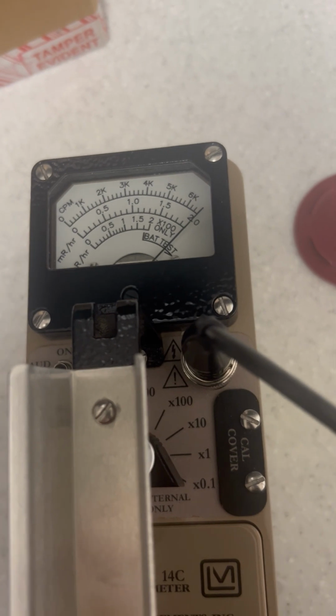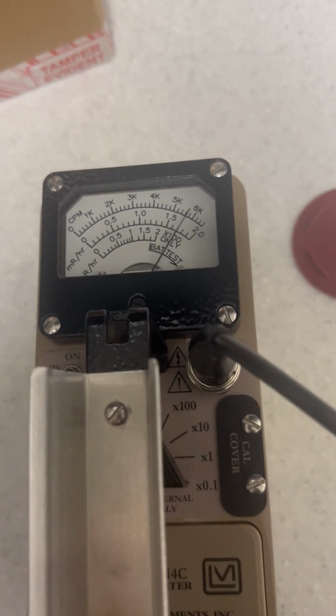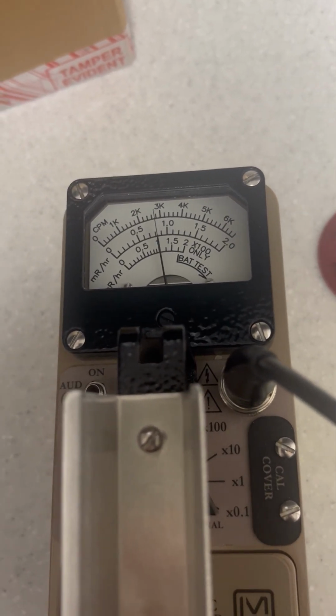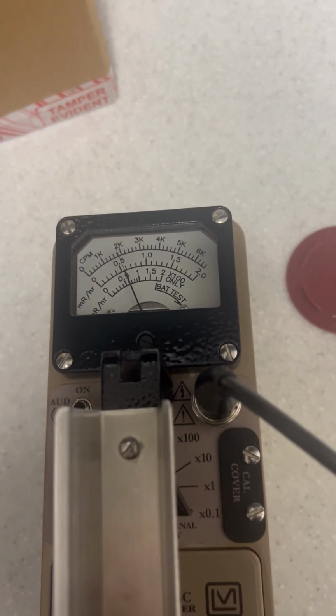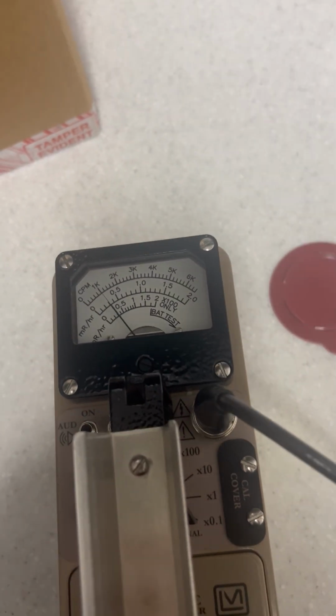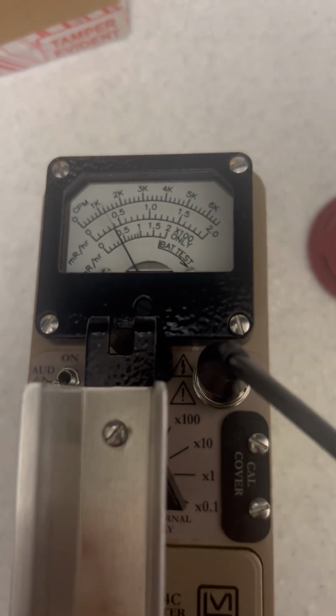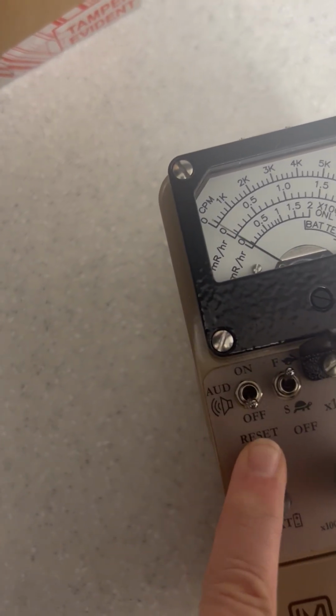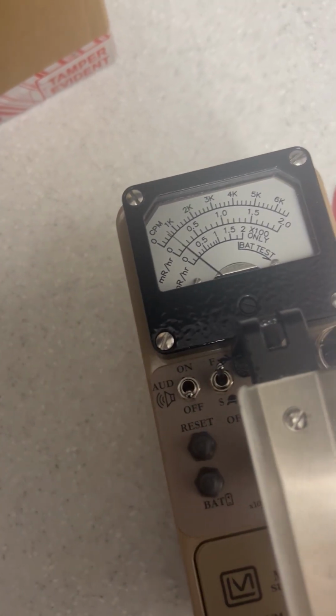I remove the probe and the needle stays at the top, and it takes a minute for it to come back down. That's because of dead time. That's where the dead time has paralyzed the system. So one thing that you can do if it's all the way at the top is to hit that reset button, and it will kind of bring it back down to the bottom.